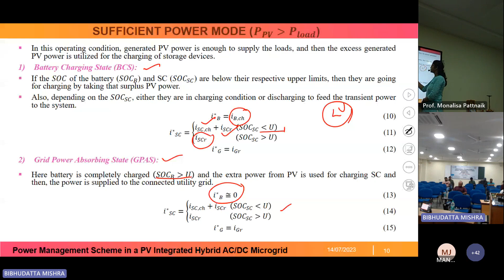When the supercapacitor SOC is less than its upper limit, it will take power for its charging, and whenever it is required in the system, it can supply the transient power to the system. When it is completely charged, it can only supply power to the system, and we stop the charging of the supercapacitor unit. A similar case will happen in grid power absorbing mode, and the respective reference grid currents are generated from the power management algorithm.